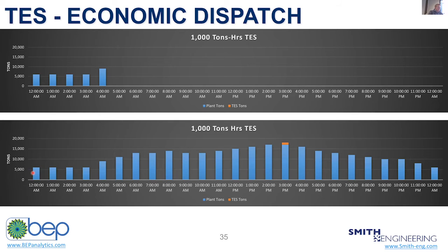So in this fictitious example that would never happen, the exact right time was 3 p.m., right? If you would have done it at 8 a.m., you would not. The optimization objective changes based on what your objective is. If you're in California CAISO, whatever your rate structures and objectives are, it's going to change. But in this fictitious example, I want to reduce my daily demand. So I should discharge the entire capacity right at 3 p.m. And if I didn't have a forecasted load profile, I would have never gotten that answer right.